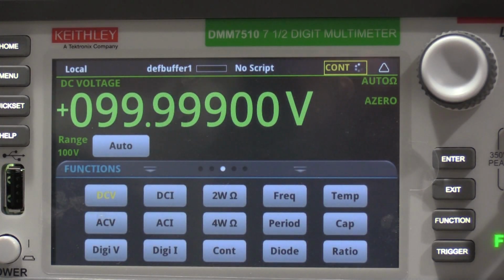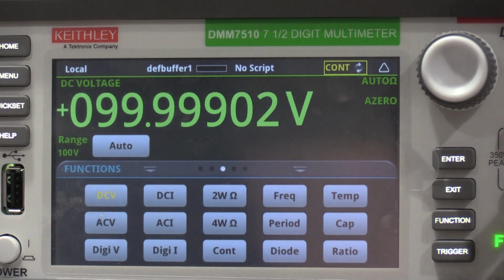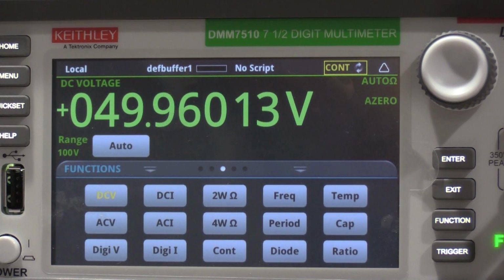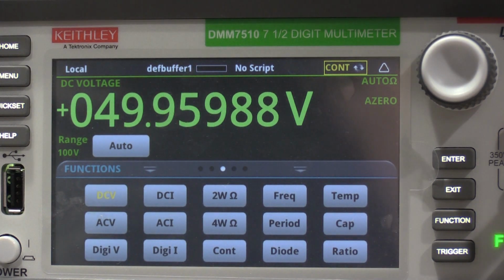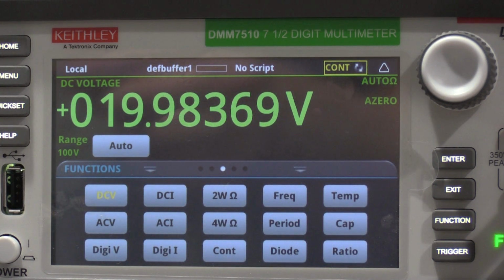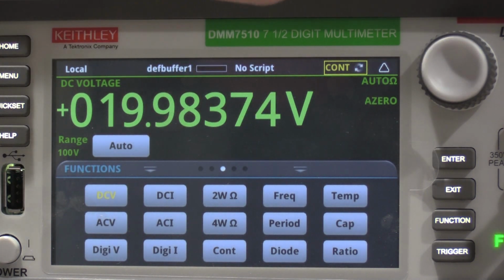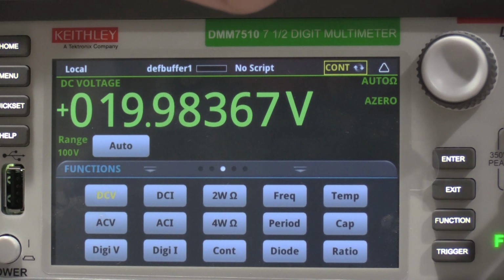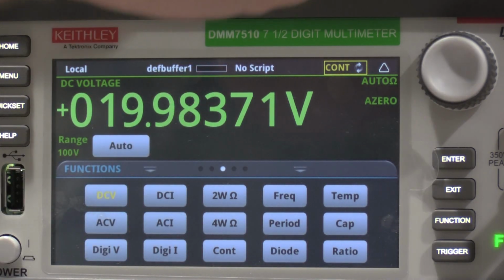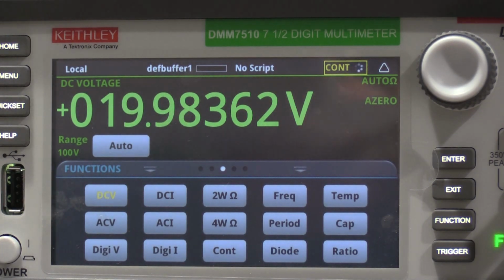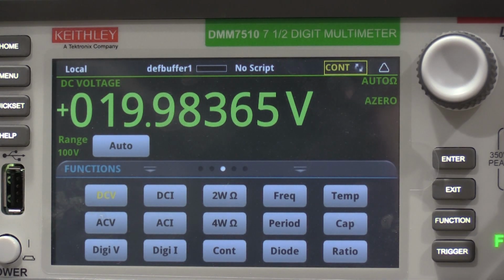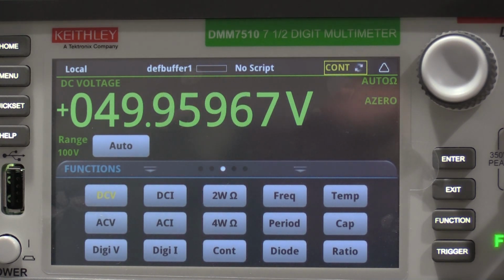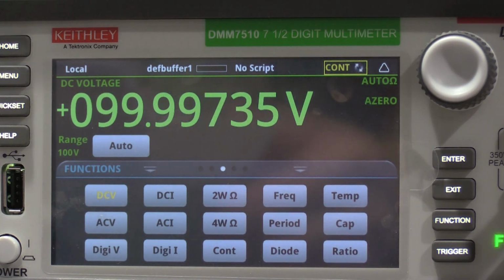Okay, now I need to check the 50 and 20. I think I want to dial it up a little bit because my 50 volts is a little low. How about my 20? I need to stop this. I'm looking at the wrong meter. 19.98, that's fine. Yeah, that's a little bit light. No, that's good. I'm allowed 925. So that's okay, yeah. So 100 volts.